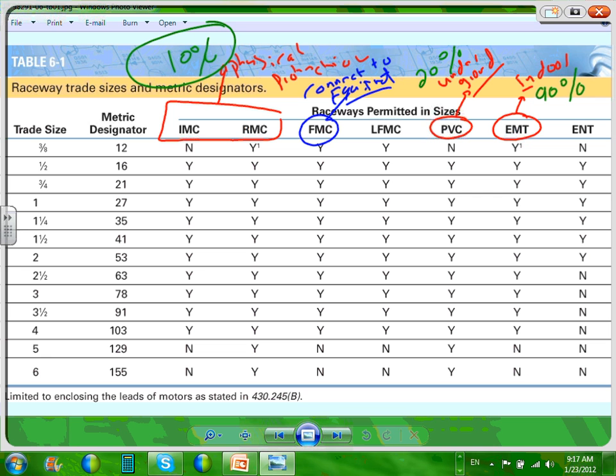Any question about that? So we have an air handling unit, right? And I have EMT conduit coming all the way right next to the disconnect on a wall, and from that disconnect I use a flexible metallic conduit for flexibility and to absorb vibration. Every time you have equipment, guys, for the ease of using the equipment, moving the equipment, maintaining the equipment, and for the reason of absorption of vibration from the equipment. All equipment has some type of moving object, a lot of them, not all of them. So to absorb the vibration, you're going to tie it with the flexible metallic conduit.